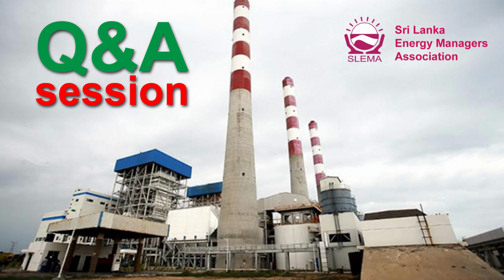Pump storage hydropower plant is one of the solutions being considered for avoiding tripping. Now, even having a pump storage power plant is not a solution for avoiding tripping, but a solution for grid stability, so that the tripping won't happen, or any of the power plant won't trip in the first place. When you have the pump storage hydropower station, you can of course make the grid much more stable, so that a synchronous generator is connected to the grid and ultimately provides more inertia to the system.